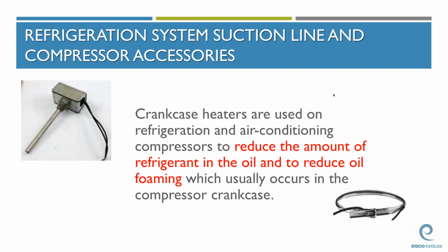Another accessory that's used to help protect the system components from damage, namely the compressor, is the crankcase heater. So crankcase heaters are used on the system to reduce the amount of refrigerant in the oil and reduce oil foaming, which can occur in the compressor crankcase. Refrigerant-laden oil is typically present in the crankcase when ambient temperature is low and the compressor is not operating. If oil foaming occurs, the lubricating capability of the oil can be greatly reduced. This can cause severe internal damage to the compressor. So in your teachings, it's important to let your students know that those crankcase heaters should be energized at least 24 hours prior to turning the system on.